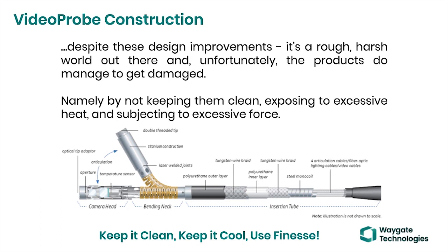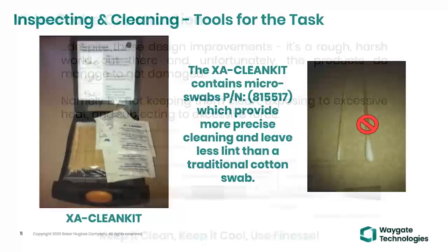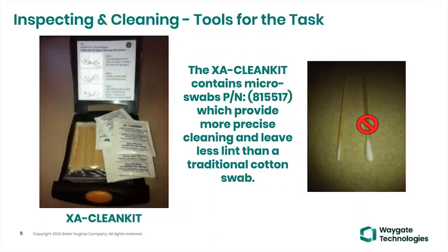Let's talk about first the cleaning component. You remember the small micro pins that I showed you in the back of the 3D phase lens? There's also an O-ring in there. And if you put a tip of your shirt or a rag or a big Q-tip in there and spin it, you're going to spin those electrical contacts right out of the back of the tip adapter, and it is not a happy ending.